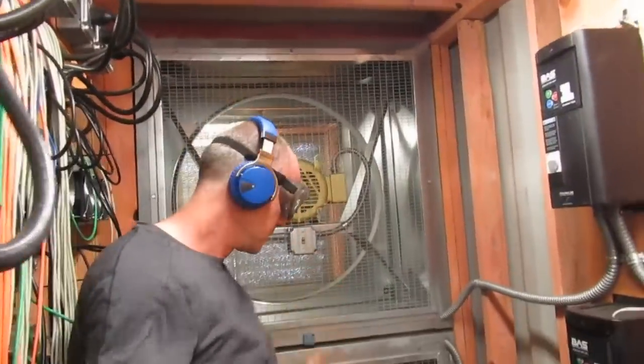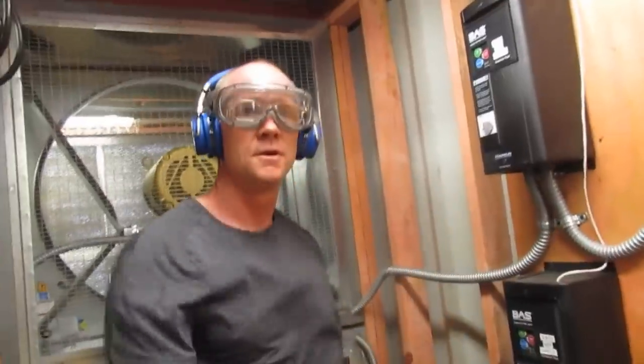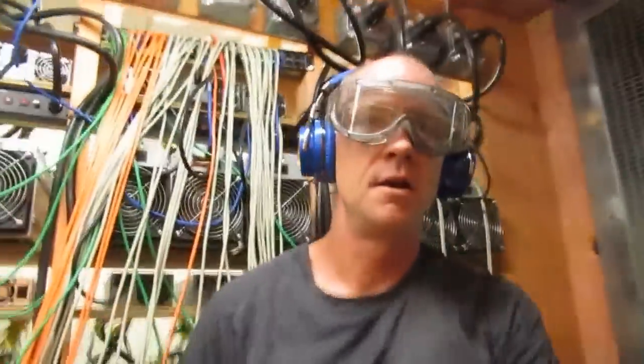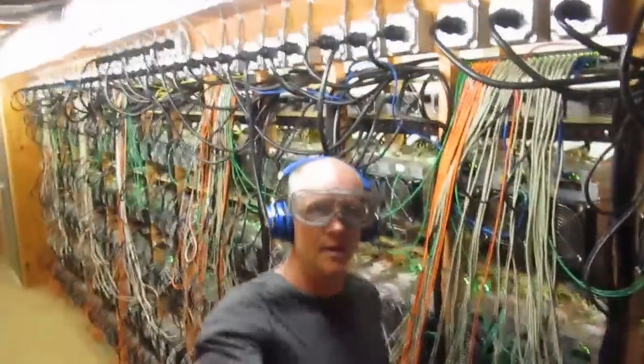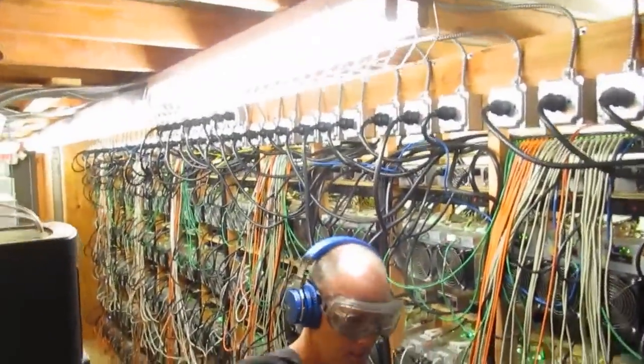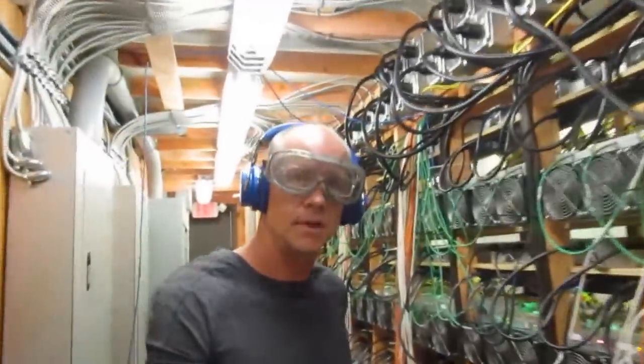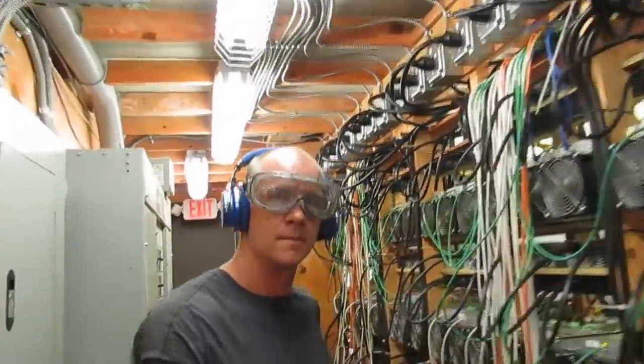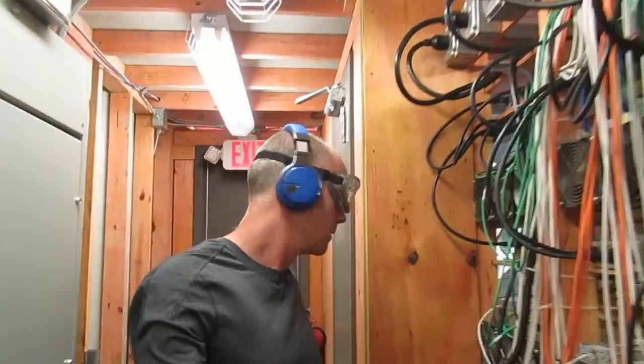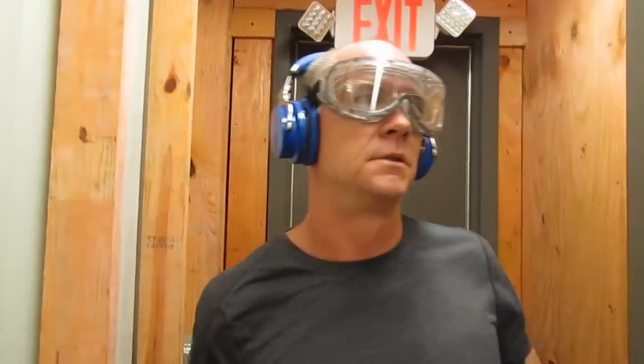Here's the intake fans. There's two of them. They're each 20,000 cubic feet per minute, so that's giving me 40,000 cubic feet per minute of intake and 40,000 cubic feet per minute exhaust. So the entire cold aisle here, oh, I was just pointing to a sensor. I measure the intake temperature and humidity as well as the exhaust temperature and humidity. So I had to do this by code, just like the other build outs in the area. I'll probably put the door in the middle next time instead of the end. Here's the two exhaust fans and the other side of the container.